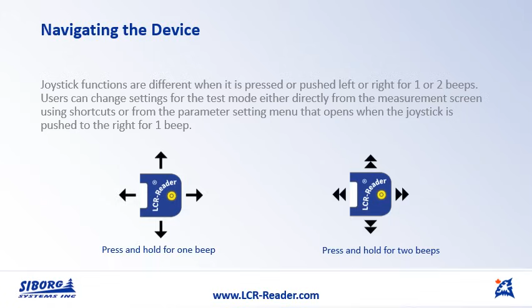For example, pushing the joystick to the right for 1 beep opens the parameter setting menu. Pushing the joystick up for 1 beep changes the primary impedance type, like R, C, L, and so on. Pushing the joystick to the left for 1 beep changes the frequency. Pushing the joystick down for 1 beep changes the signal level. Pushing the joystick to the right for 2 beeps does open short calibration. Pushing the joystick up for 2 beeps while measuring a component initiates the relative sorting measurement mode and stores the reference component value and type. Press the joystick down and hold for 2 beeps to cancel relative measurements.